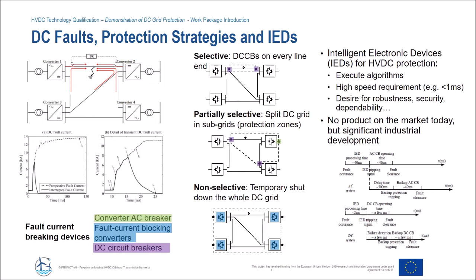Now there's no product readily available off the shelf today on the market, but there's significant development being done towards this end within work package 9 and elsewhere. The most ready comparison for these IEDs is with a traditional AC breaker, and to give you an idea of the challenge for the DC system, for an AC system you would expect the IED to have a processing time of about 40 milliseconds, whereas for a DC IED that has to be reduced down to about 2 milliseconds.